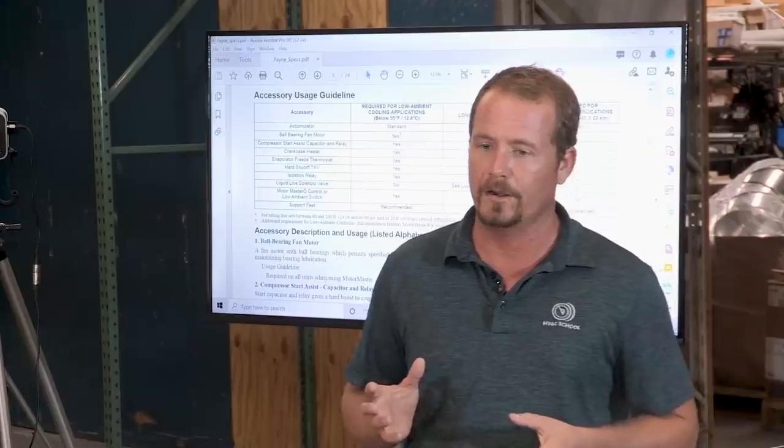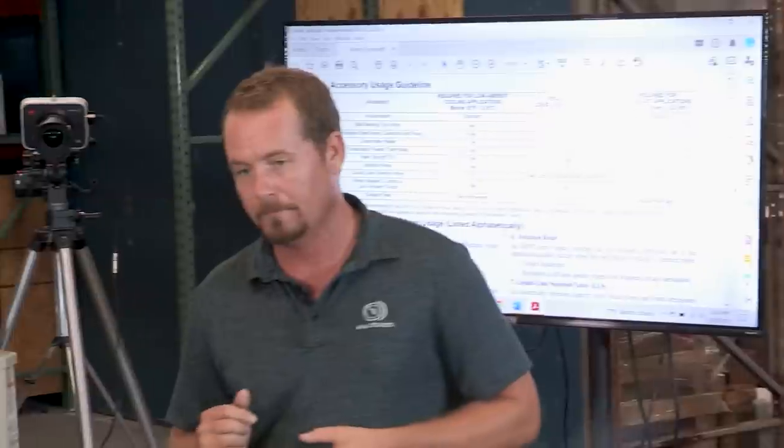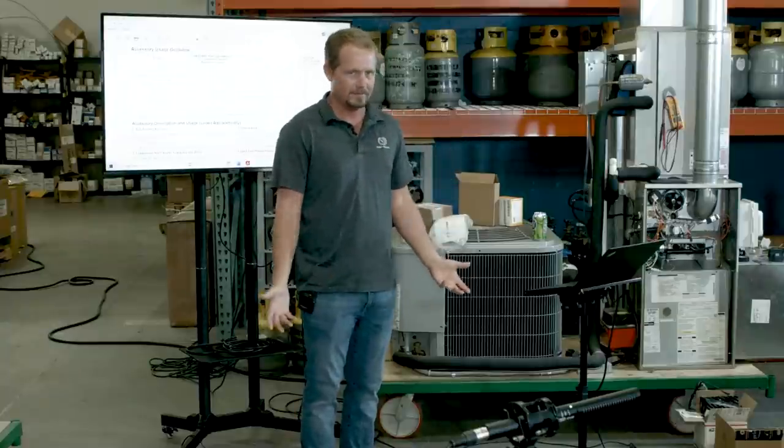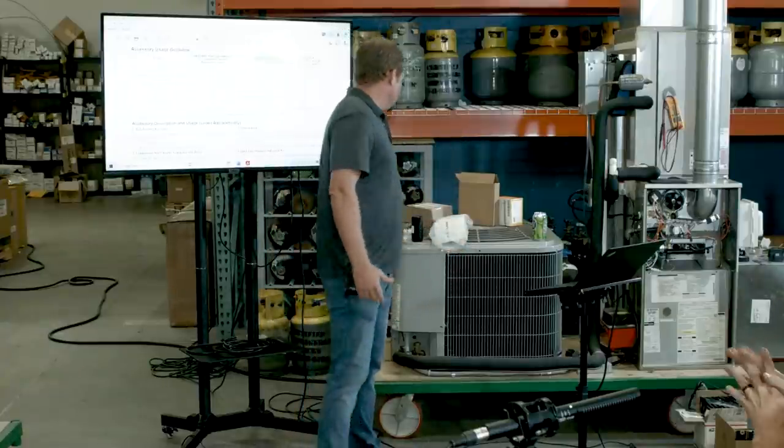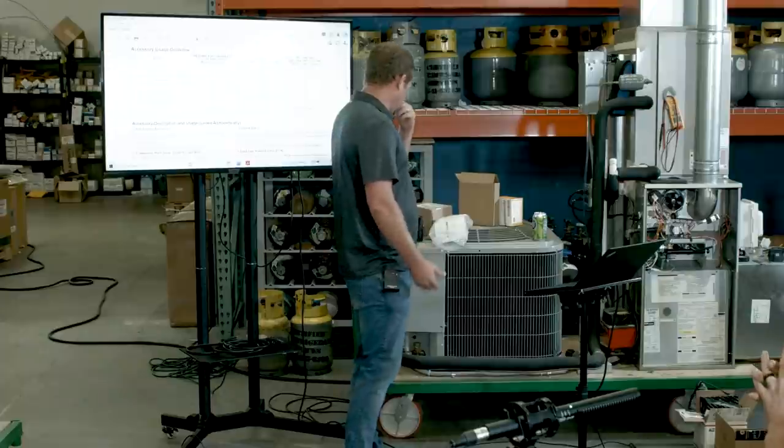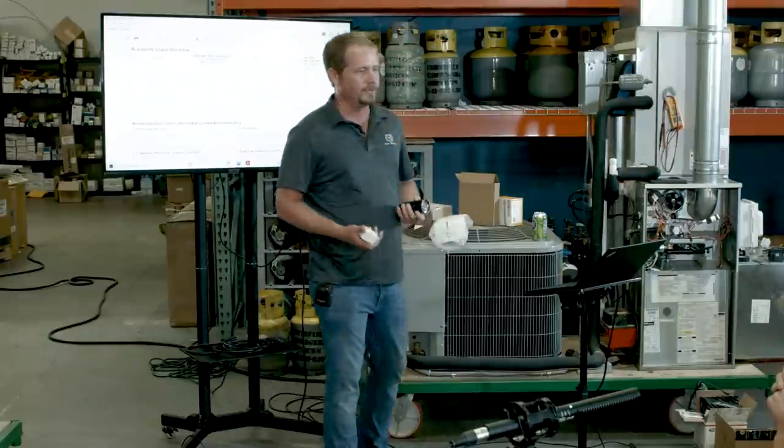What is your start winding current if you have a bad capacitor? Open capacitors, bloated up, looks like a toad. What's your start winding current? Zero. But what's your run winding current? If you measure on common and that thing's trying to start, what is it? Real high, right? So it's a misconception to think that compressor starting causes high current on the start winding. Of course, it sounds like that's how it worked, but it isn't, right? So why is it important that start gear is properly matched to the piece of equipment?